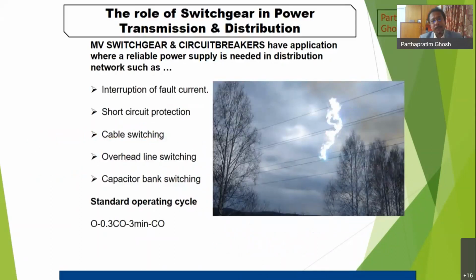Just to have a refresh, what a switchgear is and what a circuit breaker is meant to perform. A medium voltage circuit breaker is also a switch, and its function is the interruption of all sorts of faults, fault current or overvoltages. That is the major function, and that keeps it apart from other ordinary on-off switches. It's a very specialized function of a circuit breaker.